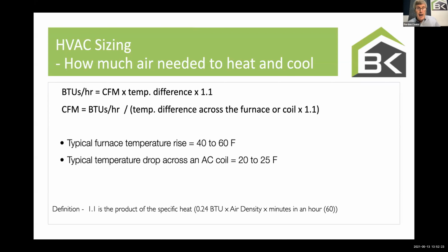Oops, sorry. In terms of how do we determine how much air we need to heat and cool, we're going to take that formula. Remember the formula, the third formula, which was the airflow formula? The number of BTUs per hour is equal to CFM times temperature difference times 1.1. If I turn that around and ask how many CFM do I need to add X amount of heat, BTUs, now the CFM that I need is equal to the BTUs, heat gain or heat loss of the room, divided by the temperature difference across the furnace or coil, and divided by 1.1. And what you need to know is a typical, at least for today, a typical furnace temperature rise is 40 to 60 degrees Fahrenheit. That is, a furnace takes in return air at 70 degrees. By the time it comes out of the top of the furnace, it might be at 110 to 120, maybe as high as 130 degrees Fahrenheit.